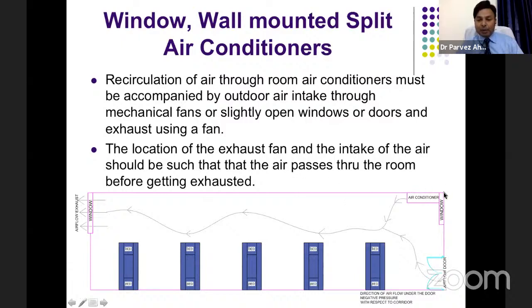I don't have a pointer, but you can see my cursor. If this is the room, one side has a window, so an exhaust fan can be installed on the other side. Air enters through the window or door, passes through the entire ward, and exits through the other corner, maintaining airflow throughout the room. Similarly, an air conditioner can be installed in one corner to maintain ambient temperature in the room or ward. When the air conditioner runs, it throws air across the room, and the exhaust extracts air from one side, maintaining the ambient temperature inside the room or ward.